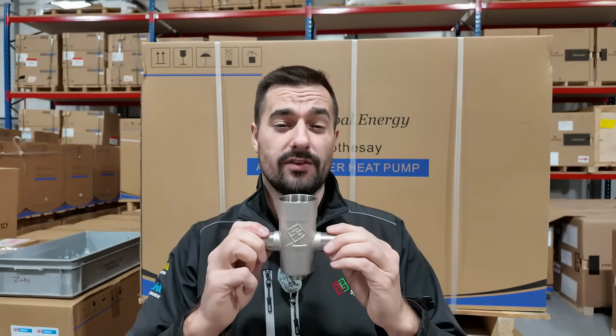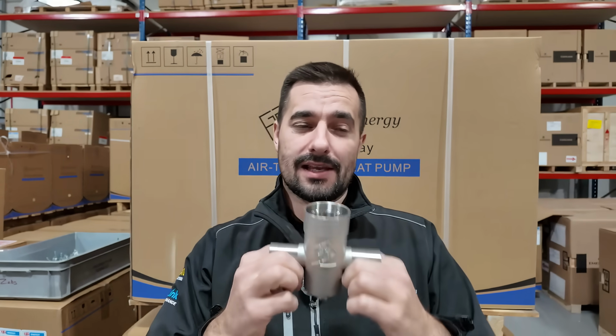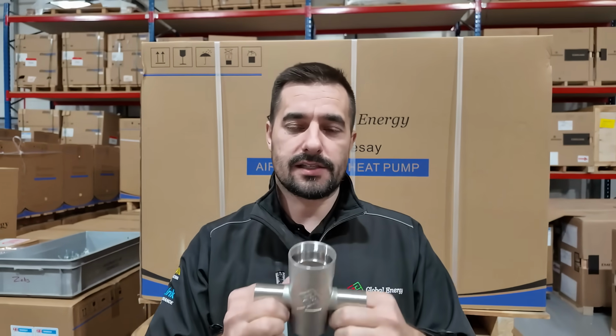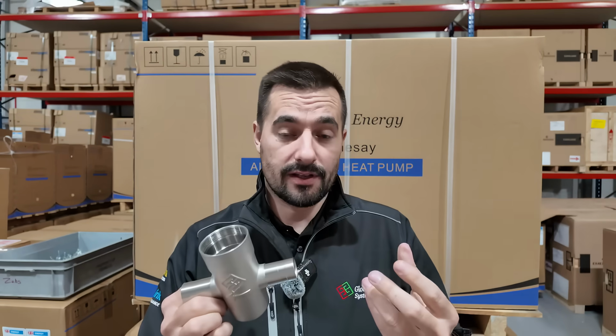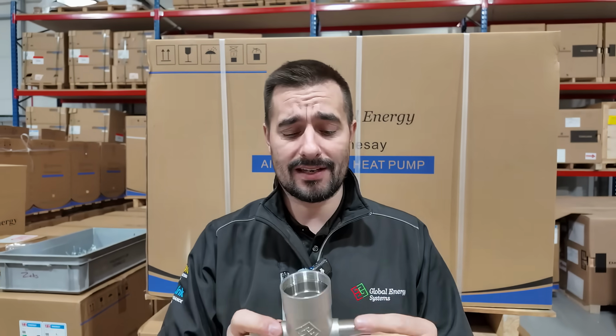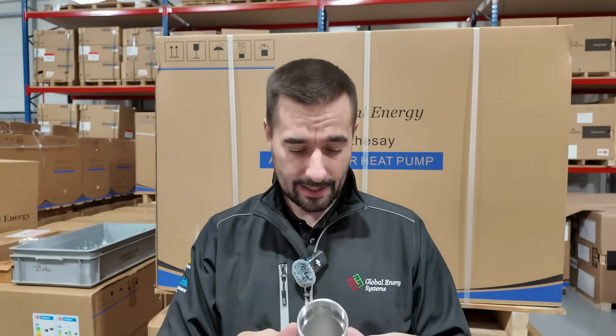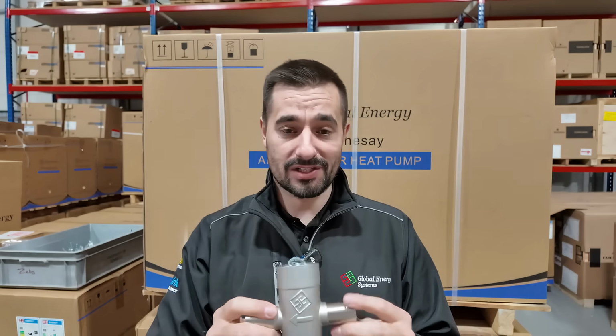Now, the other thing that I like about it is it is stainless steel, and stainless steel is obviously robust. We put a 25-year warranty on this. Again, the plastic filters that are out there, I'm not keen on plastics in heating systems because I feel that they do become brittle over time. You know, 10 years down the line, if you're pulling out a plastic magnetic filter, I've had them fail on me, O-rings have split. It's been a nightmare. This thing's pretty solid and reliable.